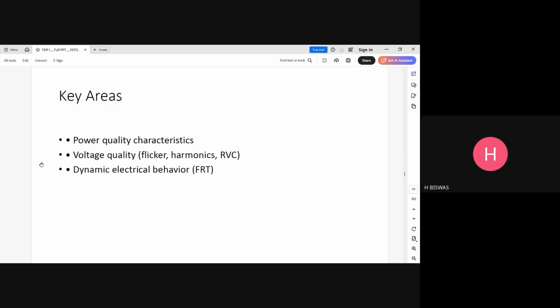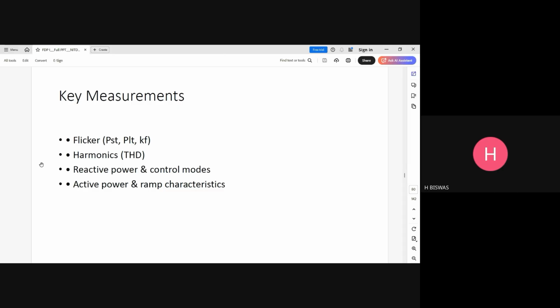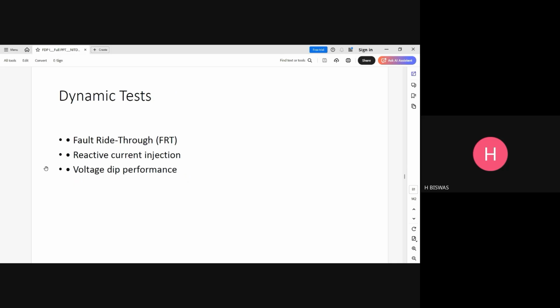So key areas: power quality characteristics, voltage quality, flicker, harmonics, RVC, dynamic electrical behavior. Of course, FRT is there. Key measurements: flicker, harmonics, reactive power and control modes, active power, and ramp characteristics. Ramp, obviously, you are aware of. These days, even ramp rate is a talking point for thermal power plant generators as well, because when renewables are injecting into the grid, thermal operators are asked by the regulators to go for variable speed rather than base load. So that is one of the things to balance the grid, actually. So it's a complex situation.